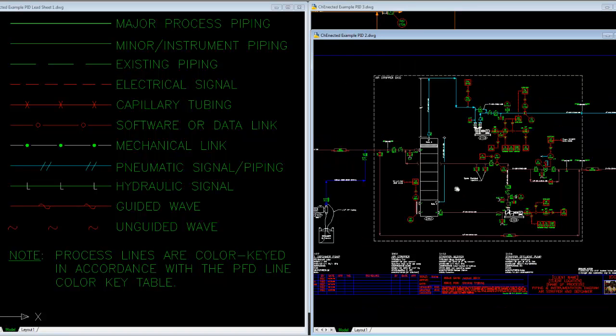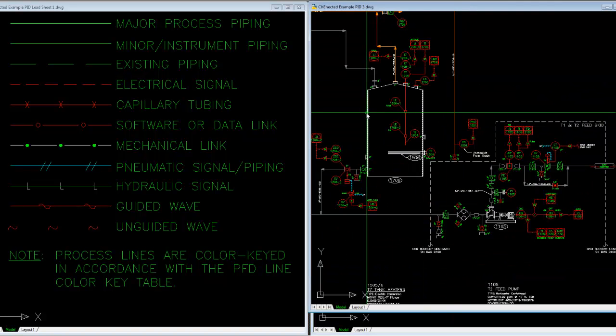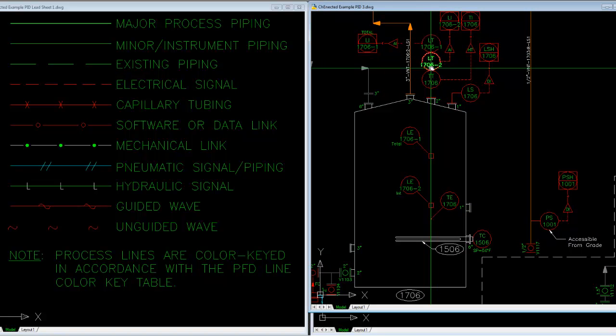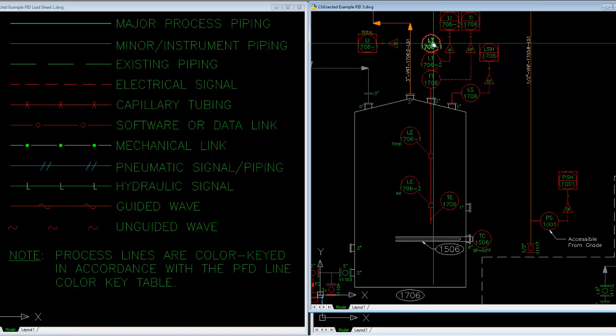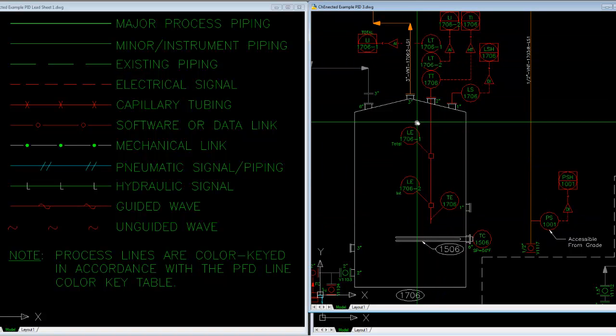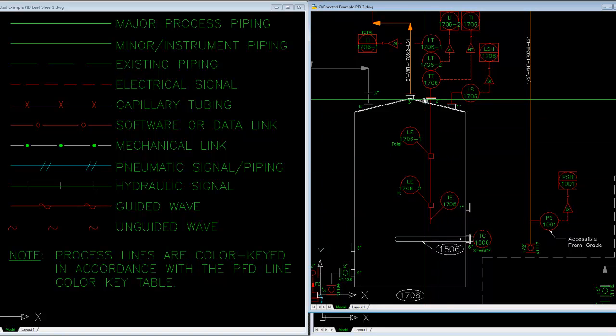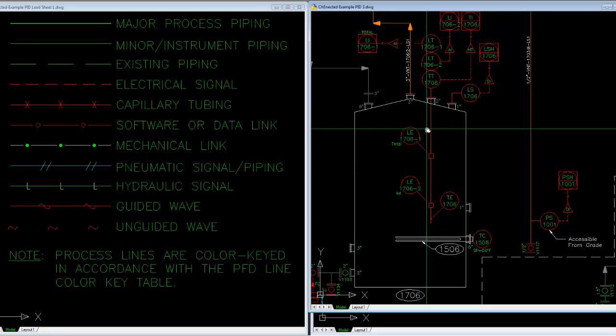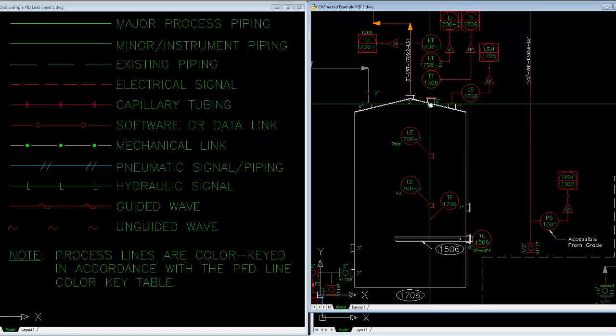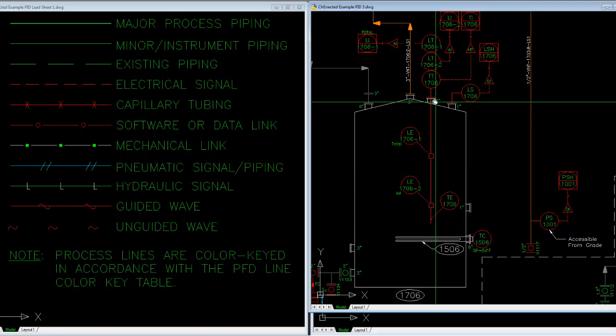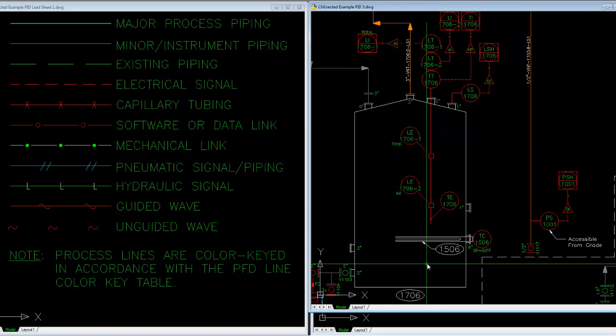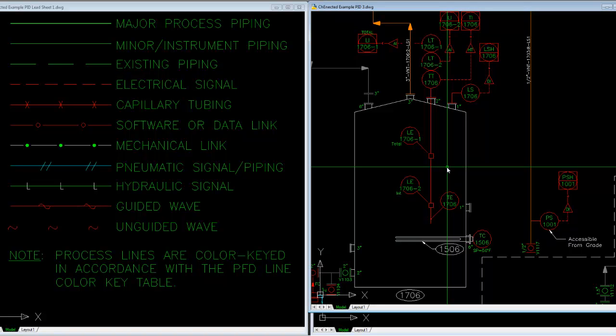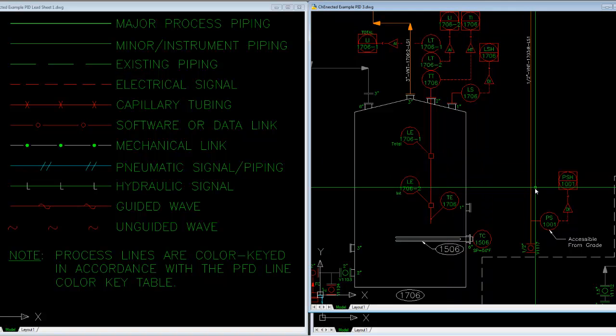I don't think I have any examples, but it's not hard to imagine where if, for example, level transmitter 1706, one and two, which are now shown as floats, were unguided radar. I might replace this whole assembly with just a simple horn and show these unguided symbols coming down, which would help illustrate that that's a guided wave or unguided wave radar. Is it important from the standpoint of interpreting the P&ID? Not really, because we're not really getting into what specific type of instrumentation are we trying to show. We're really just more focused on the understanding what is provided and how it interfaces with the plant at a high level on P&IDs.